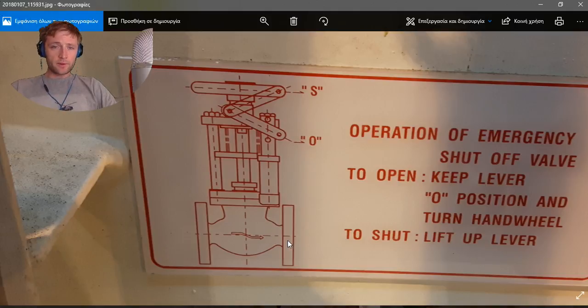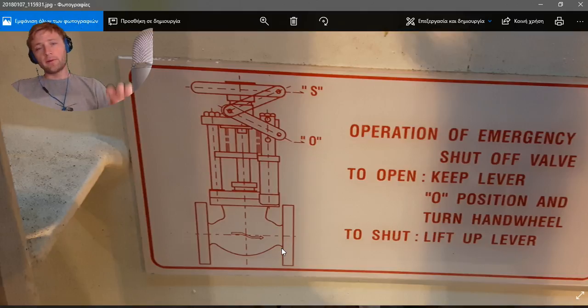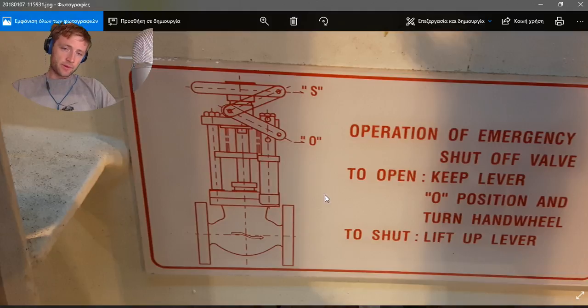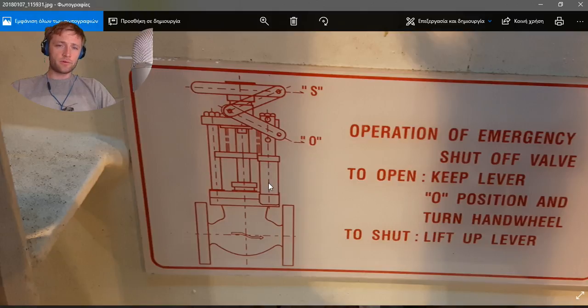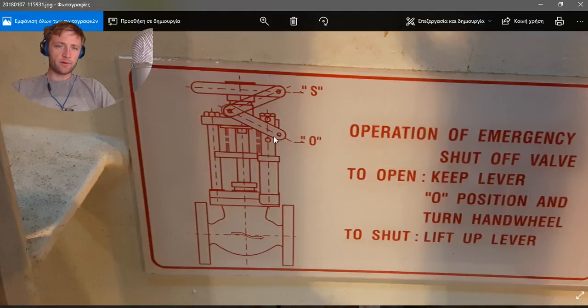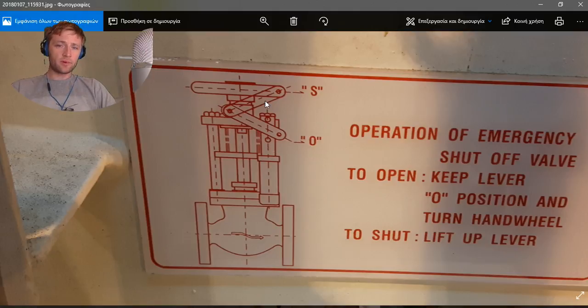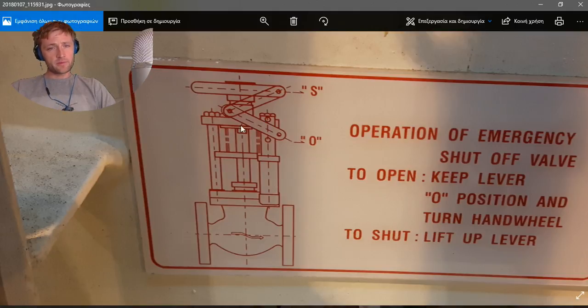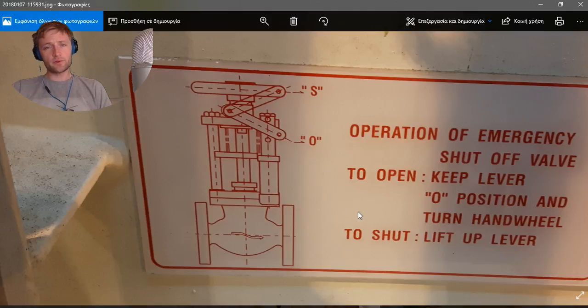This makes it easier to keep the ship under control and under working procedure, and to isolate the problem at that moment. When we activate the lever on the quick closing valve cabinet, air travels through a copper pipe and pushes the piston inside. The lever, which is connected by the bracket and some pins, will lift up, and then the spring — which is under tension — will press the valve down and close it.